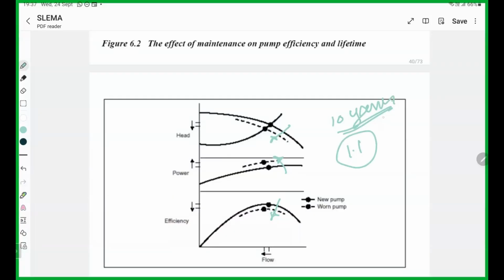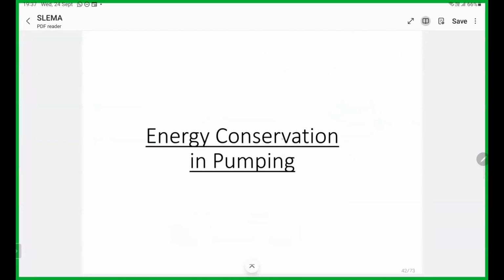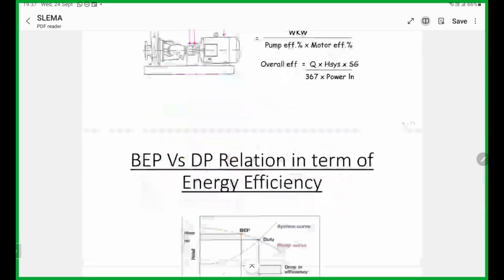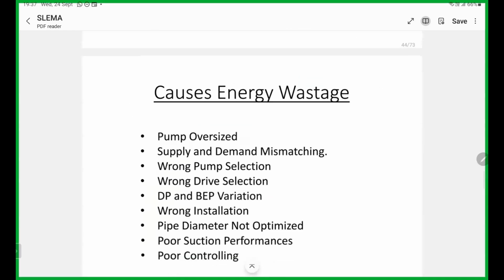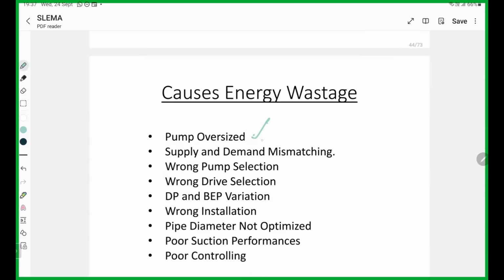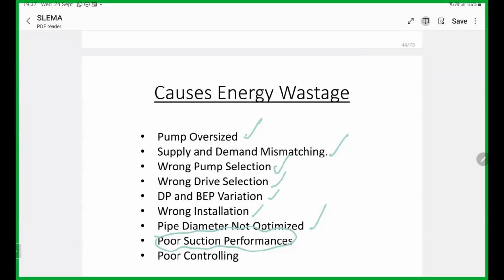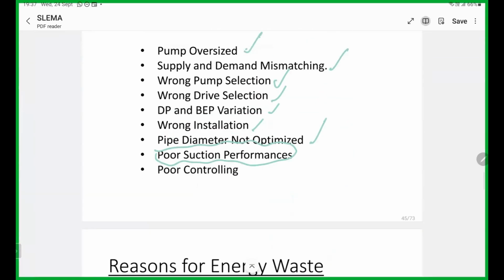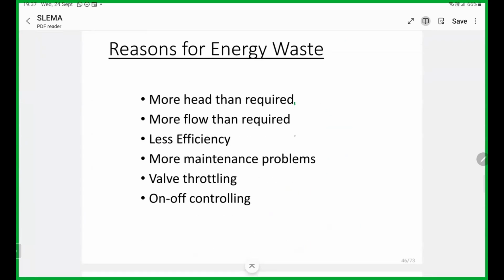If the pump power is very close to the motor power, then in future you will be in trouble, right? Then energy conservation in pumping, which we already discussed. In my experience the pump is oversized, and supply and demand are not matching. Wrong pump selection, wrong drive selection, duty point and best efficiency point variation, wrong installation, pipe diameter not optimized, and poor suction. The important one is poor suction performance, and poor controlling. When you come to energy conservation, you have to think about those things. Energy waste comes from more head than required, more flow than required, and less efficiency.